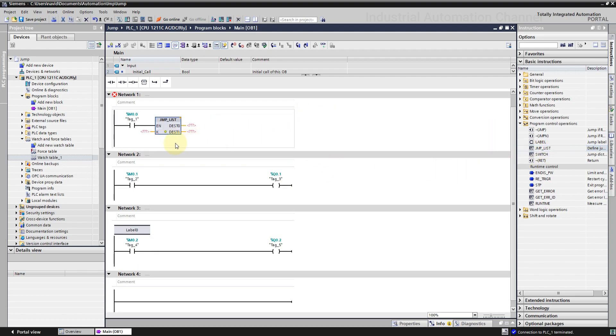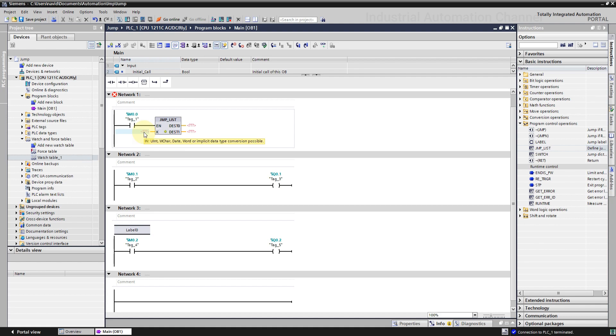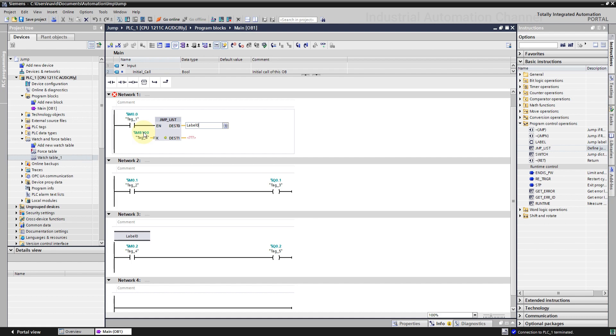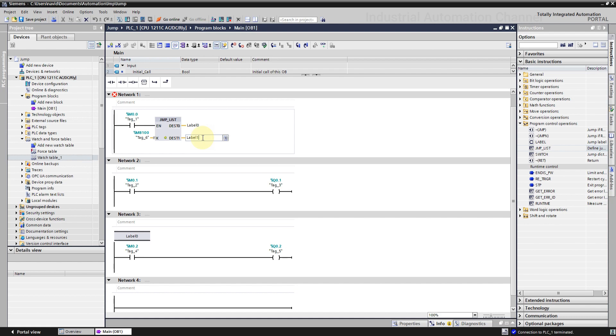In this case, we can choose which jump to be executed in our program using this input key. It means if the key is, for example, 0, the jump in destination 0 will be executed. With the key 1, the jump will be done to the destination 1 and with 2 to the destination 2. Define a variable for the key. Destination 0 is label 0. Let's create two new networks with a label.